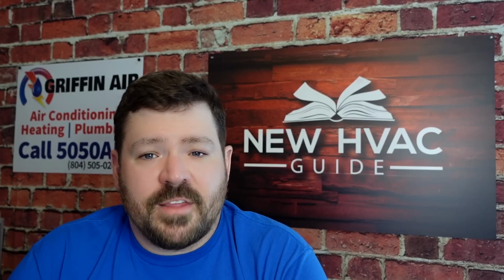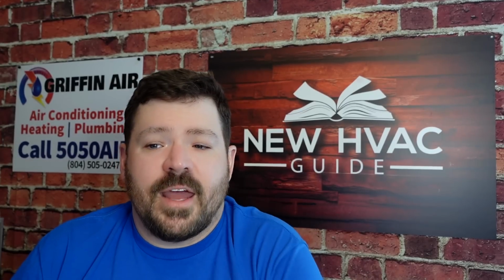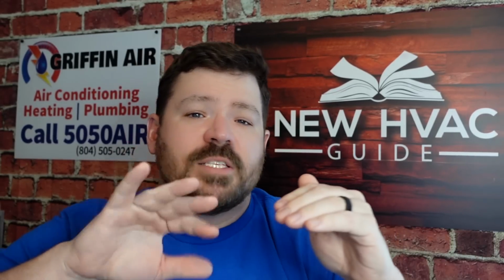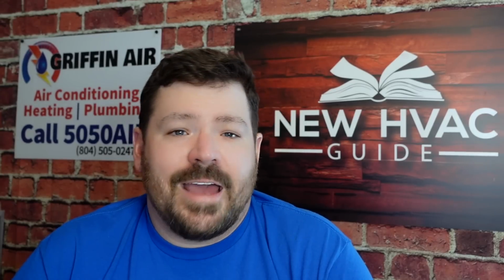They're going after it all. This is not just residential systems. They're going after chillers. They're going after ice makers. They're going after anything that creates cold air or water. This is going to affect that in the next several years. The other thing that's interesting is with that whole 700 GWP, with some of these other products like chillers or ice makers, we are seeing a different GWP rating being attached to those. Some of them are as low as 150, where they're saying that if you have an industrial refrigeration system, the highest GWP you're going to be allowed is 150. So they are really making these changes. They've now given us a date, they've given us a timeline, and this is a sign of things to come.